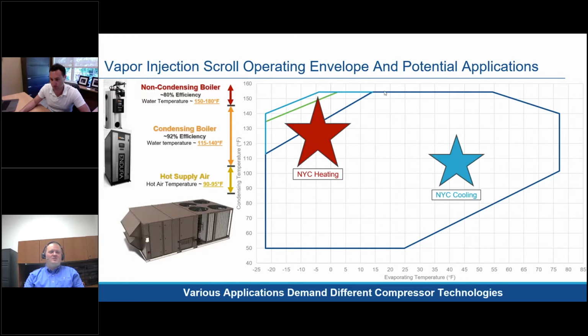But as you can see, this is a general example of what we call a vapor injection operating envelope. You can see some limitations on what that max condensing temperature is, and that's generally going to limit what hot water or hot air temperature you can make. Typically, in order to make hot air, you can probably use the typical scroll compressors out there today. Especially variable speed compressors allow you to run at lower evaporating temperatures and higher condensing temperatures that way. But as you'll see in the presentation, there are still benefits in increasing capacity by doing some type of injection with the compressor itself.